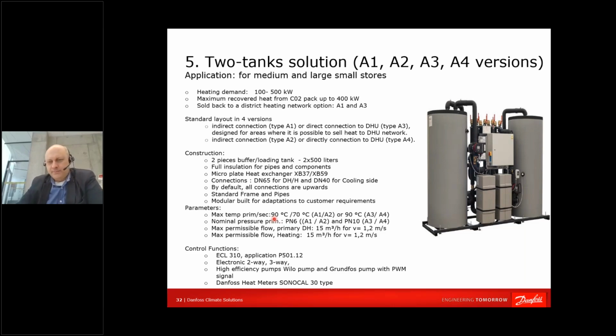I was discussing with the plant, and we agreed that they will produce a special unit on our inquiry with larger temperature, 120 degrees. The difference is you can see these ball valves, which are made in the row 2, 2, 2. So we have 6 ball valves. Actually, we need 2 of these ball valves to be changed to welding ball valves, or ball valves made from steel, which could be welded to the district heating utility primary side. So that is in general changing the status of the station to 120 degrees.